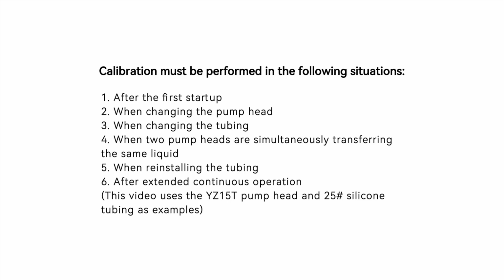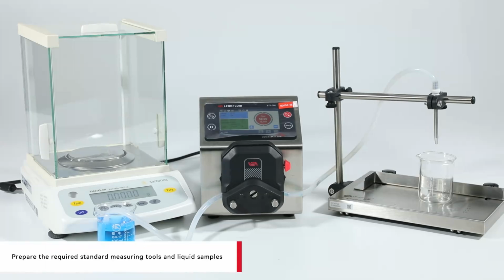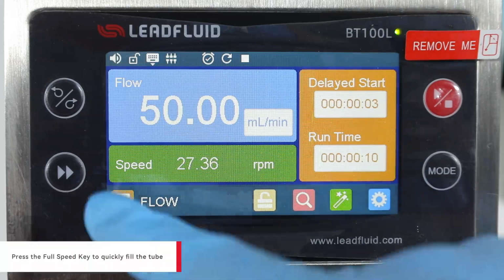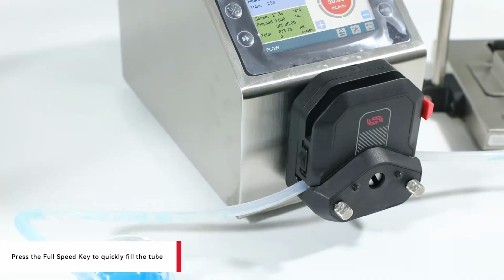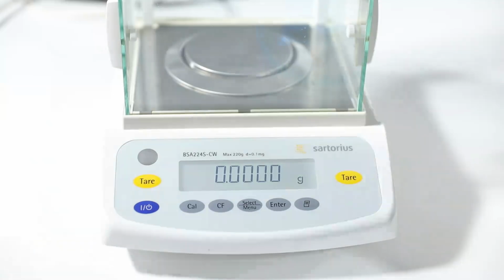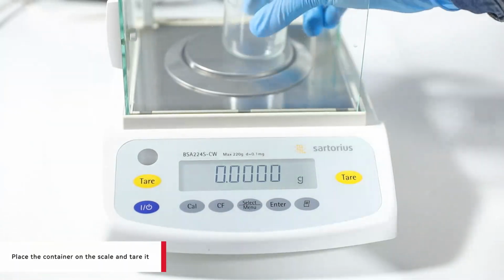This video uses the YZ15T pump head and 25 silicone tubing as examples. Prepare the required standard measuring tools and liquid samples. Press the full speed key to quickly fill the tube. Place the container on the scale and tare it.